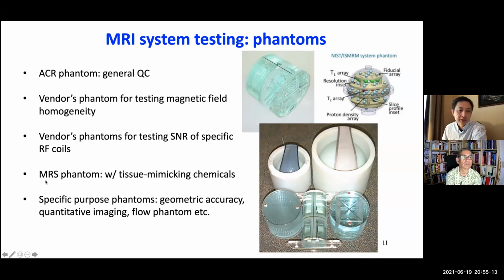And then we have the spectroscopy phantom. Within the spectroscopy phantom, we need to have chemicals that can mimic tissue metabolism. So I will show you one example of the spectroscopy phantom result. And there are other specific purpose phantoms, for example, the geometric accuracy phantom. Here is a homemade geometric accuracy phantom. You can also purchase this kind of phantom from different vendors. Usually those are designed for radiation therapy treatment planning purposes, for example, the gamma knife quality control.